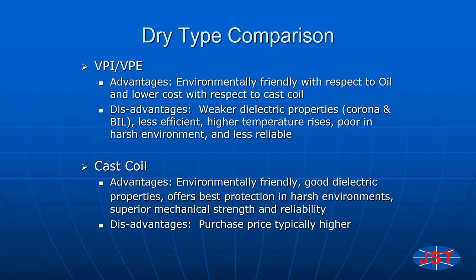We will now contrast some of the features associated with dry type transformers. Starting with VPI and VPE, we find these to be more environmentally friendly than oil-filled and less costly than cast coil. Disadvantages, however, can be seen in their performance. Weaker dielectric properties result in relatively lower BIL ratings and a higher level of partial discharge. They also run hotter and are not as reliable in harsh environments.